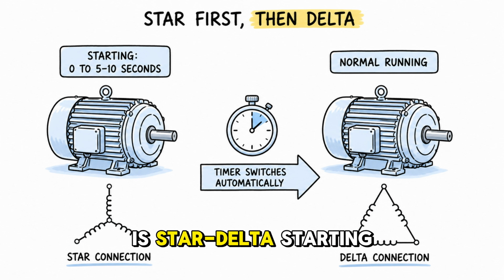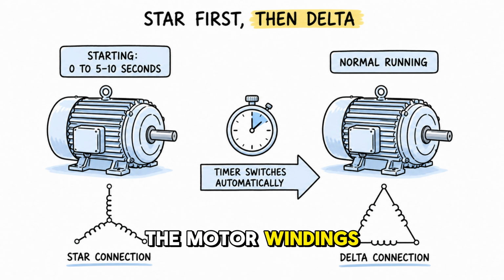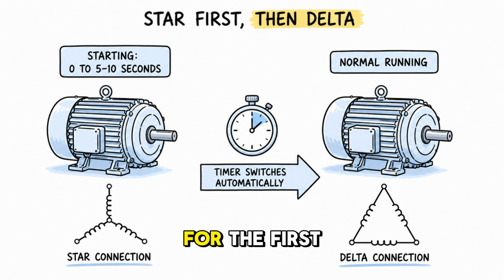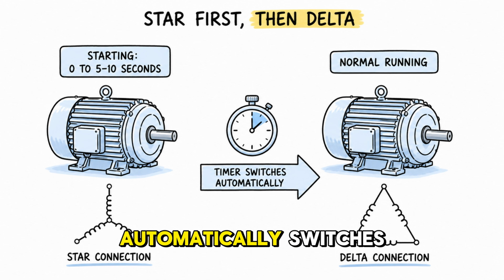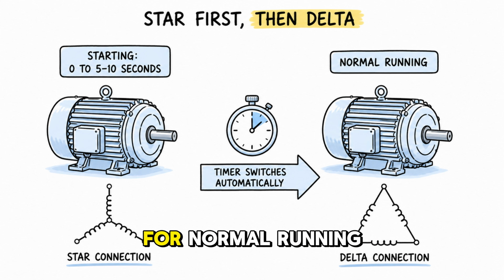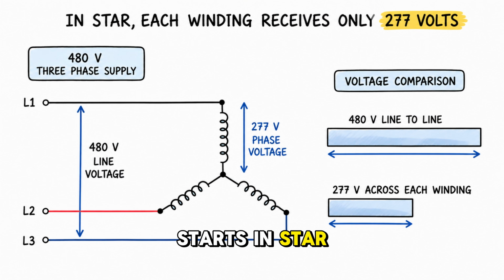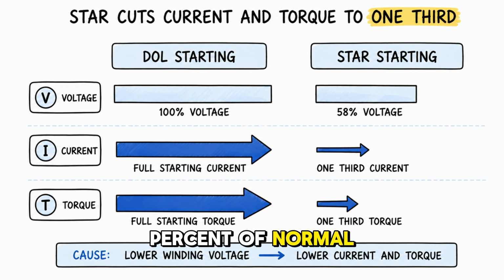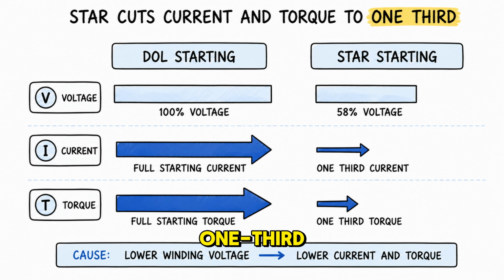The second method is star-delta starting. The motor windings are first connected in a star configuration for the first 5 to 10 seconds of starting. Then, a timer automatically switches them to a delta configuration for normal running. When the motor starts in star, each winding receives the phase voltage of 277 volts instead of the full line voltage of 480 volts. The voltage is reduced to 58% of normal. Because of this, the current is reduced to 1/3 of the DOL starting current. The torque is also reduced to 1/3.